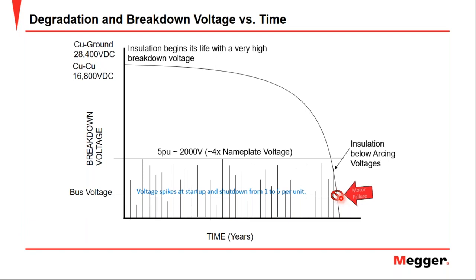So you may wonder, if the high voltage tests are the ones that give the most information, why should I perform the low voltage test? And the answer is very simple, because the IEEE 95 standard indicates that the high voltage test can only be performed in a predictive focus, of course, as long as the motor has passed the low voltage test. So at the end of the day, if we understand this graph, we will understand the structural basis of the electric motor static test.